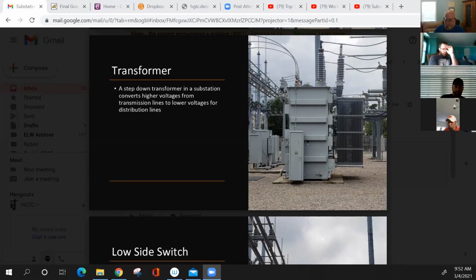On this transformer here, you'll see some current transformers, CTs and PTs up there. We talked about that too. That's what they use to monitor the amps going through the transformer as well as the volts, to make sure it stays in that range we like to have, plus or minus 5%. That's very important as well.